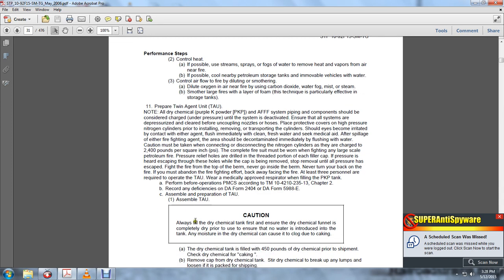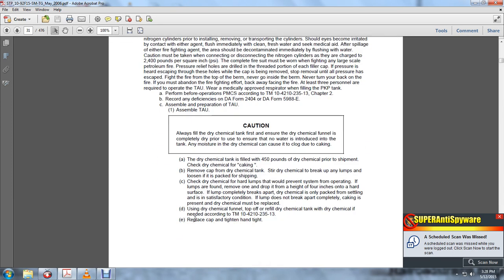Assemble in preparation of the twin agent unit. Assembling a twin agent unit. Caution: always fill dry chemical tanks first. Ensure that the dry chemical funnel is completely dry prior to use. Ensure that no water is introduced into the tank. Any moisture in the dry chemical can cause clogging and caking.